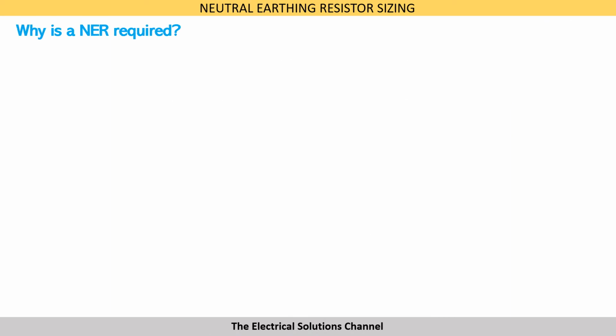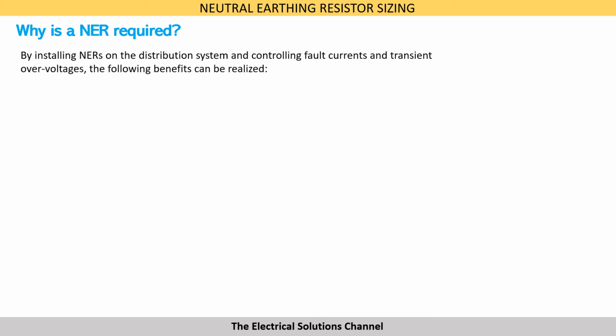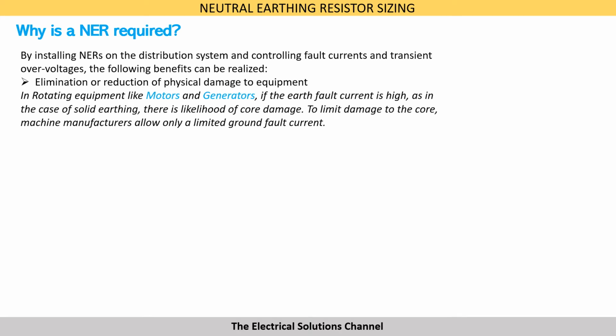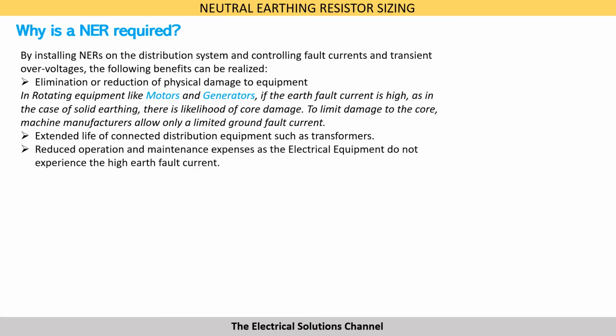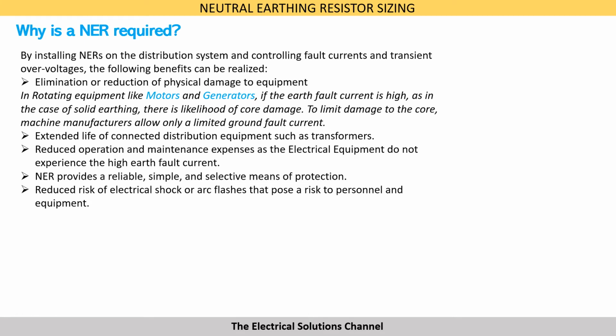So why do we need a neutral earthing resistor? Well, an NER helps in reducing the fault current, thereby enabling many benefits to the electrical system, such as reduction of physical damage to the equipment, extended life of connected distribution equipment such as transformers, reduced operation and maintenance expenses as the electrical equipment do not experience a high fault current. NER provides a reliable, simple, and selective means of protection. It reduces risk of electrical shock or arc flashes that may pose a risk to personnel and equipment.